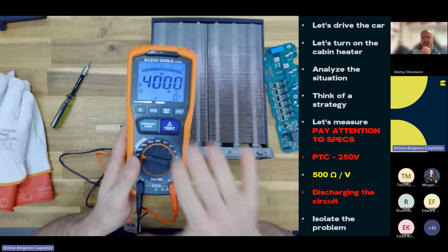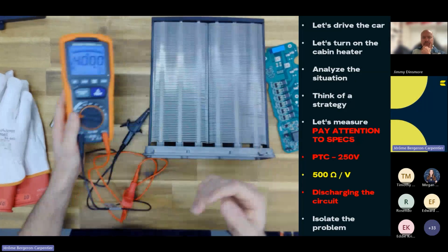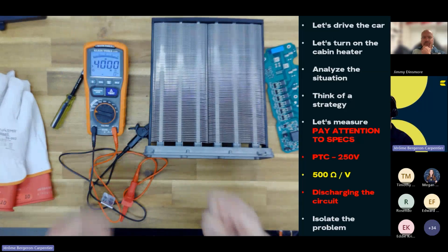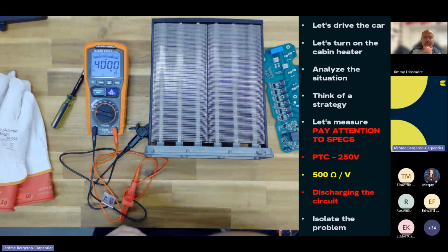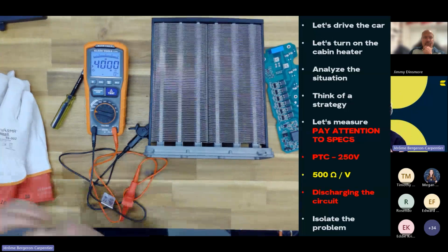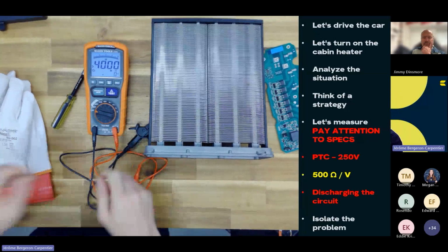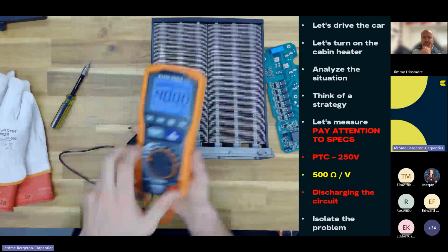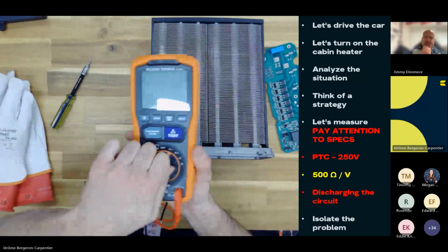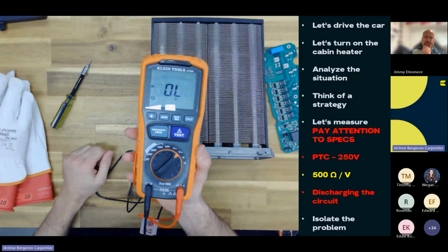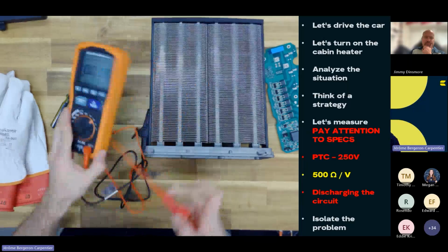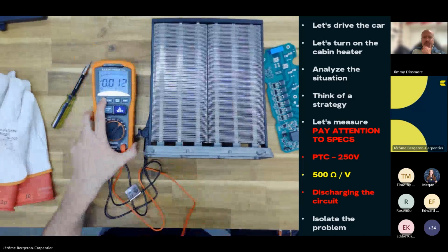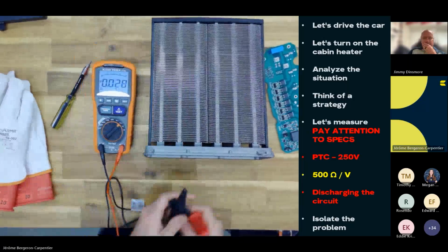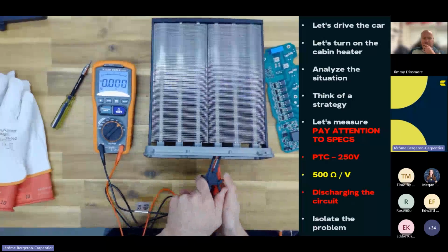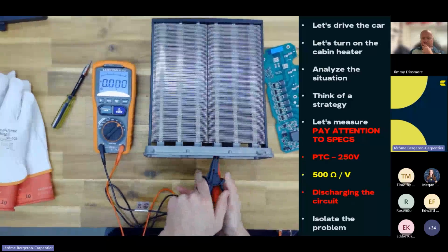And if your meter doesn't show you that here, you can, for example, after testing it, wait about, let's say, 5 to 10 seconds max, and we can just take a meter, put it back to volts, so let's say DC volts, and we're just gonna go back to the pins that we just tested and see if there's any voltage left.